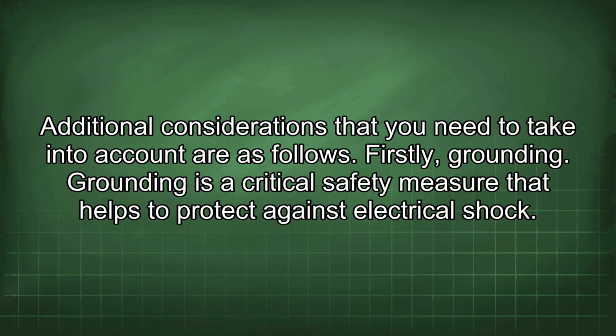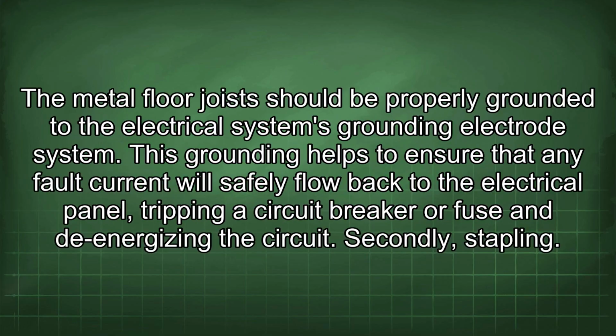Additional considerations that you need to take into account are as follows. Firstly, grounding. Grounding is a critical safety measure that helps to protect against electrical shock. The metal floor joist should be properly grounded to the electrical system's grounding electrode system. This grounding helps to ensure that any fault current will safely flow back to the electrical panel, tripping a circuit breaker or fuse and de-energizing the circuit.